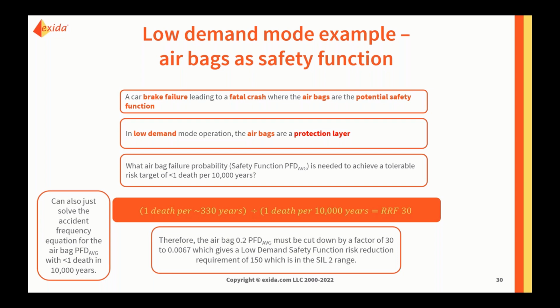Now, in actual statistics, there is a specific cutoff point between low demand and high demand mode that unfortunately the standards have glossed over, and that is if most failures are identified by testing, low demand PFD average is a better description of SIL, and the safety function is better described as a low demand protection layer.